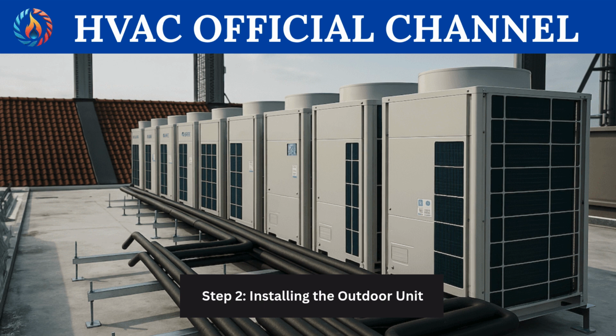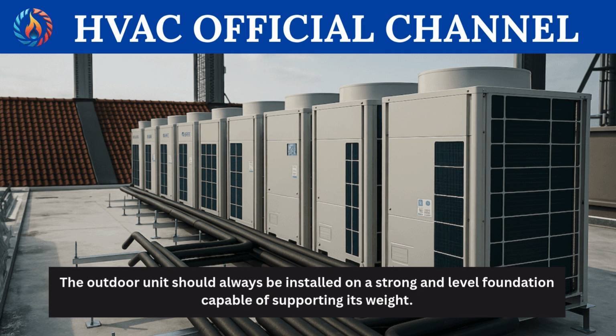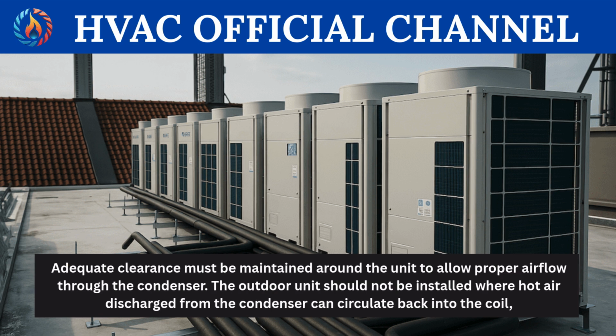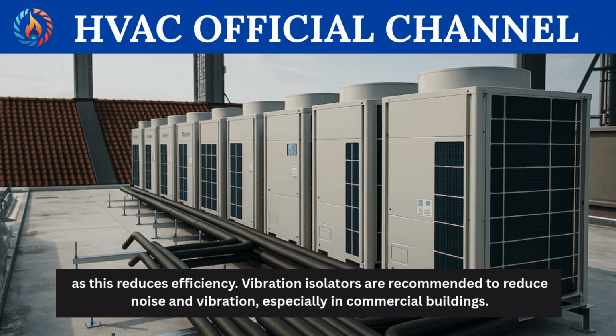Step 2. Installing the outdoor unit. The outdoor unit should always be installed on a strong and level foundation capable of supporting its weight. Adequate clearance must be maintained around the unit to allow proper airflow through the condenser. The outdoor unit should not be installed where hot air discharge from the condenser can circulate back into the coil, as this reduces efficiency. Vibration isolators are recommended to reduce noise and vibration, especially in commercial buildings.